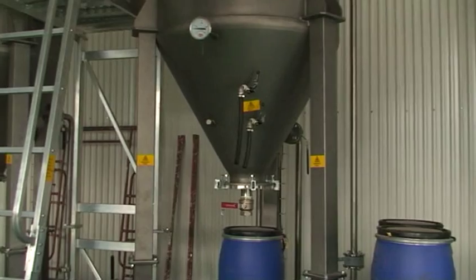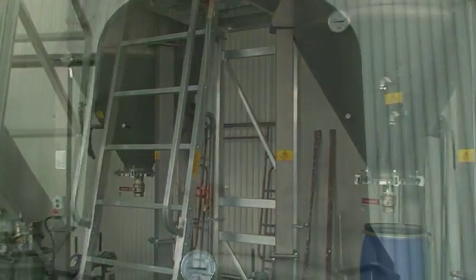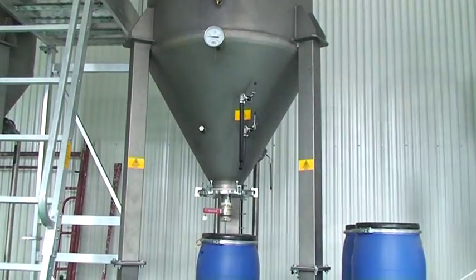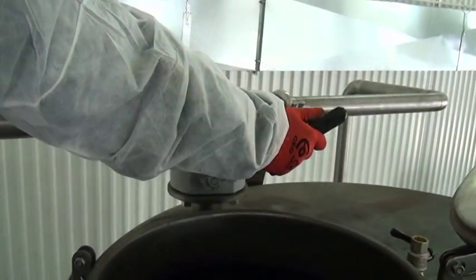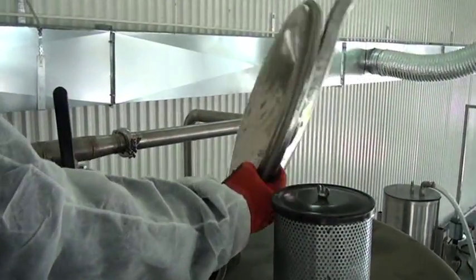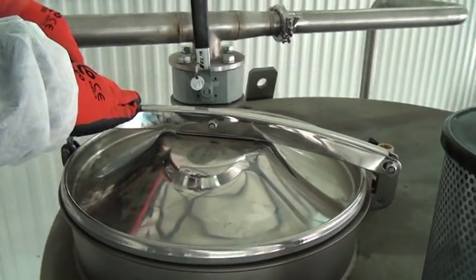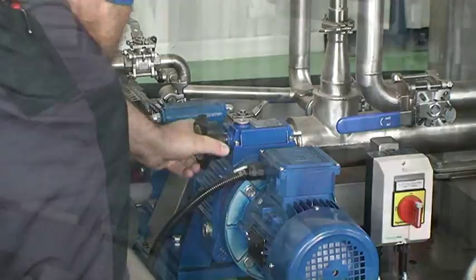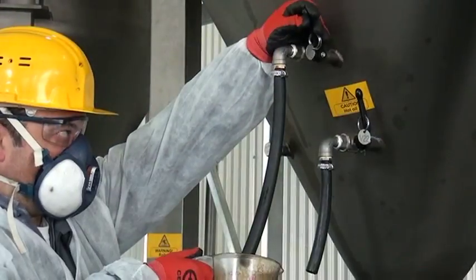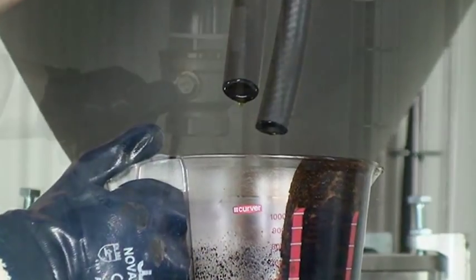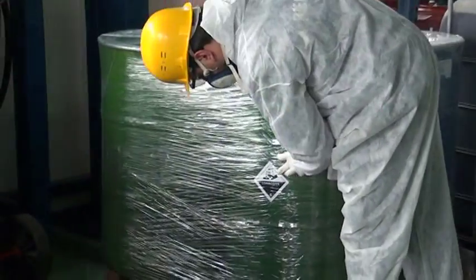Decanting or settling. When the chemical dehalogenation has taken place, the mixture of oil, spent reagent, and byproducts is delivered to the settling tanks for the gravity segregation of the reagent. At the end of the separation, the oil is pumped through a filtration stage and delivered to a storage tank, while the spent reagent and byproducts are properly packed, labeled, and temporarily stored until final disposal.